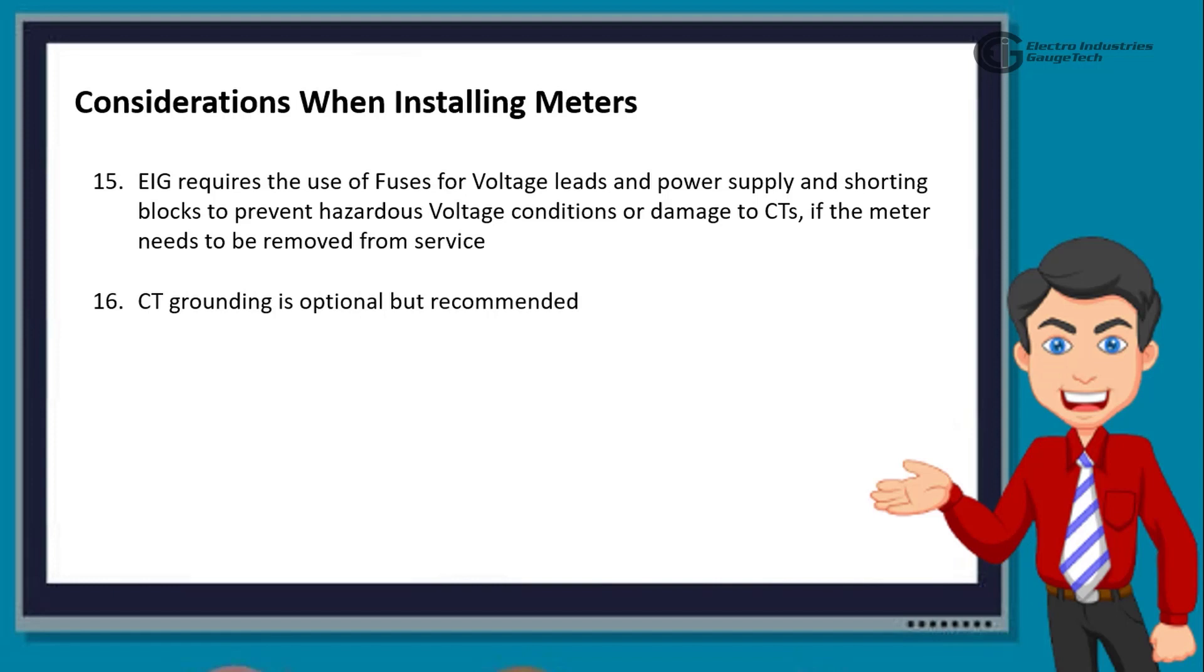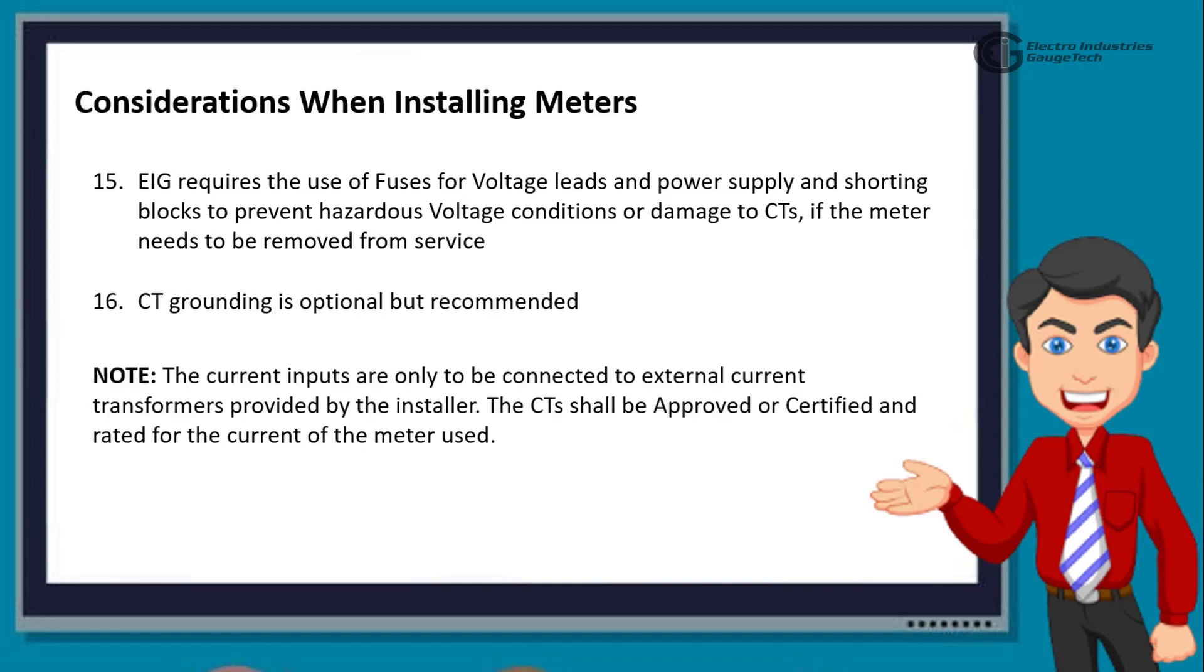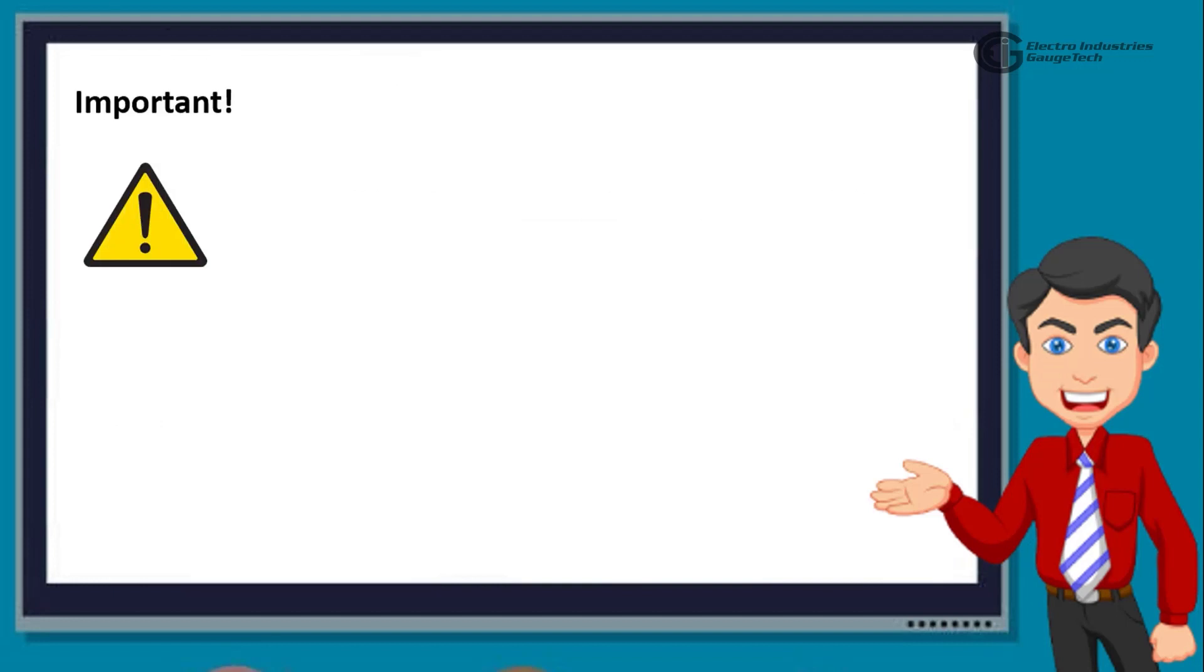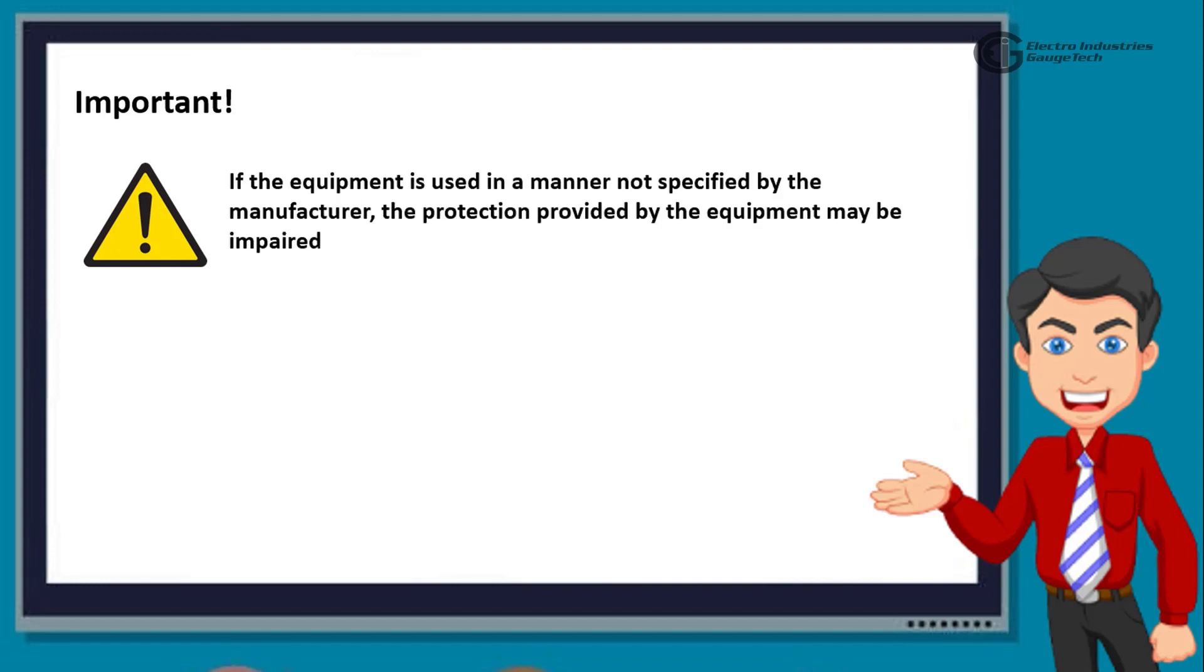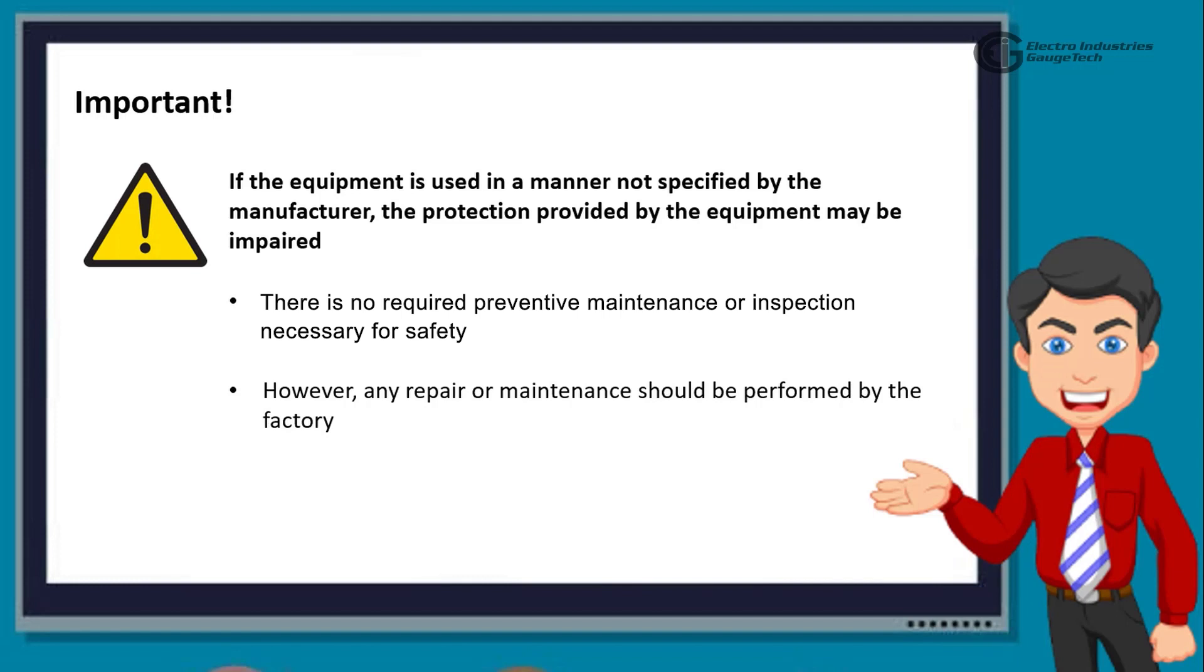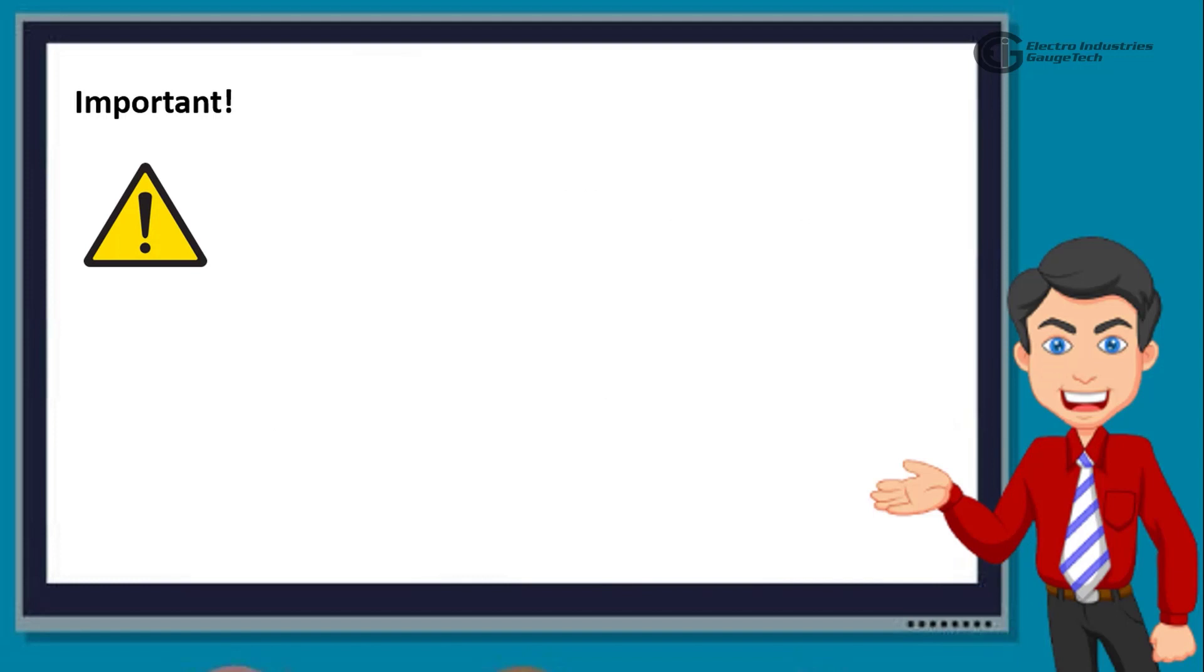CT grounding is optional but recommended. Note that the current inputs are only to be connected to external current transformers provided by the installer. The CTs shall be approved or certified and rated for the current of the meter used. A few important things are also required to be taken into consideration. If the equipment is used in a manner not specified by the manufacturer, the protection provided by the equipment may be impaired. There is no required preventive maintenance or inspection necessary for safety. However, any repair or maintenance should be performed by the factory.